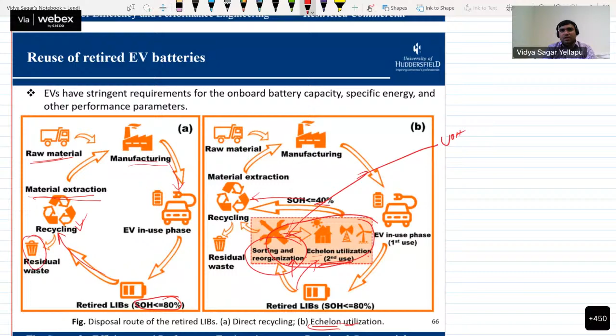Whatever it may be, cell-level echelon utilization is not recommended from the perspective of economy and safety. There are two other levels: stack level for bigger energy storage systems, and module level for smaller ones. Cell level is for much smaller systems, but this is not recommended because of the high labor required, and it is also not safe for the environment due to residual waste, nor economical. So safety is the important factor in echelon utilization.